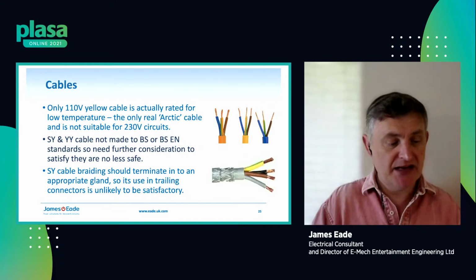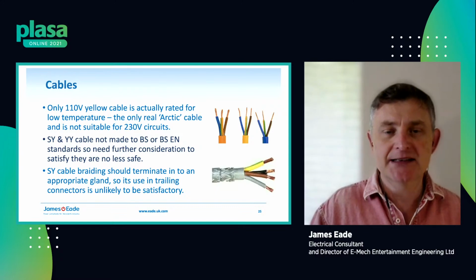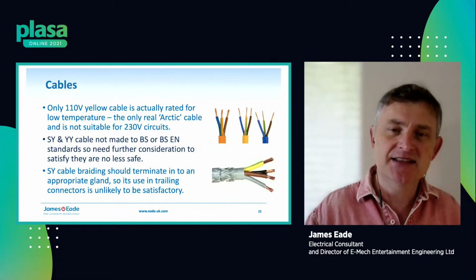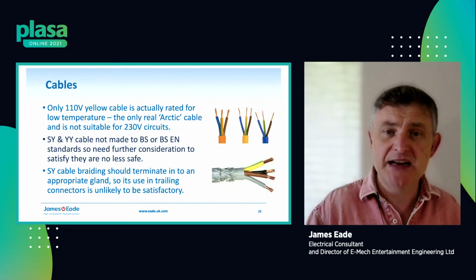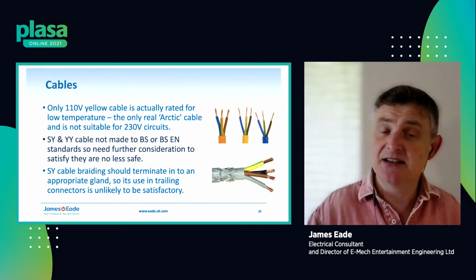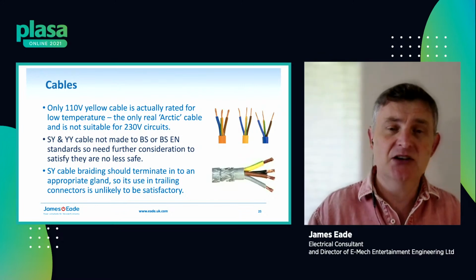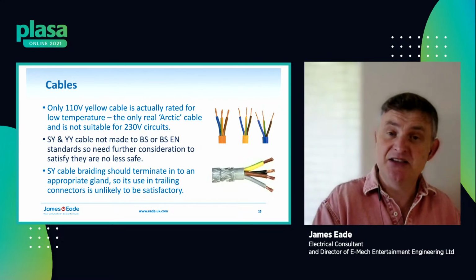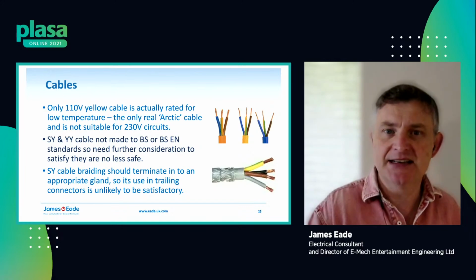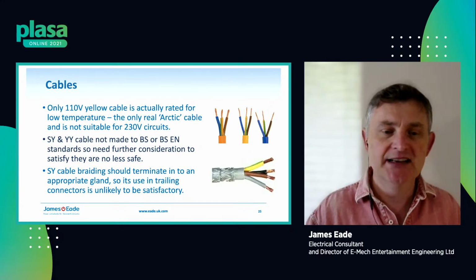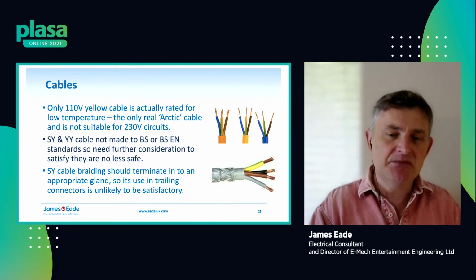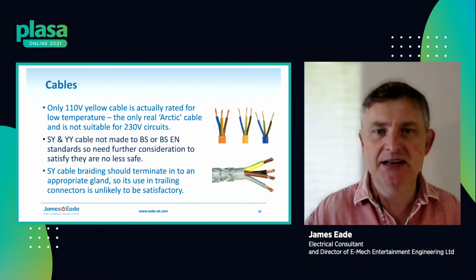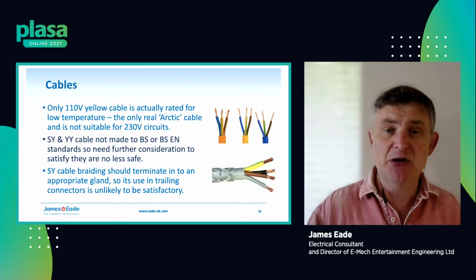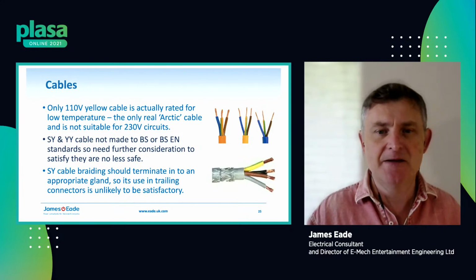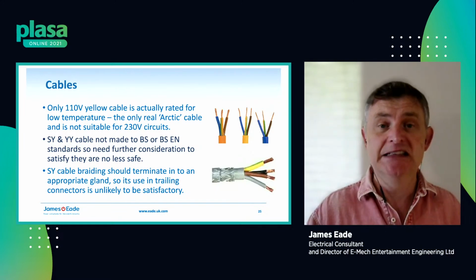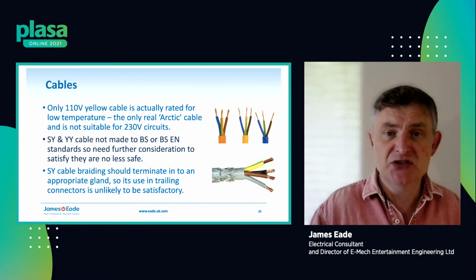On the previous slide, you saw a bit of SY with a CEEform on either end. Now, CEEforms don't have metal cable glands. So in theory, you need to do a pigtail off the braid, connect that to the protective conductor, because the braid must be earthed with that type of cable as well, which really lends itself to being used in metal cable glands and hence permanent installations, rather than with a plug and socket on either end. So it's very not suited for temporary events, and shouldn't be thought of as a flexible armored cable, because it isn't. That's not what it was designed to do. It is effectively just a plastic cable with a screen over the top of it.